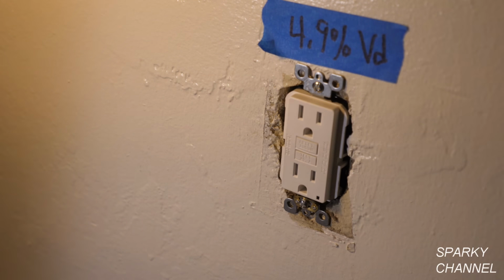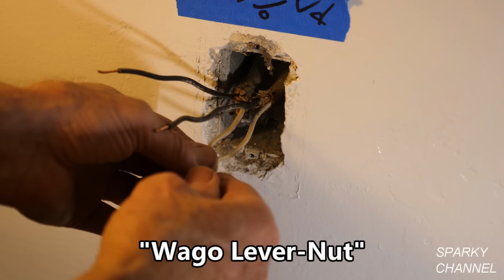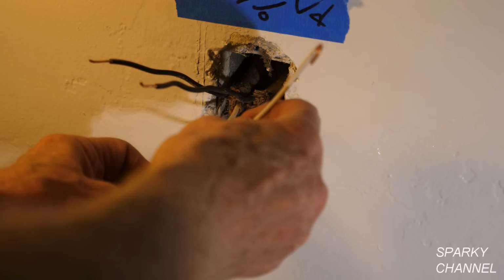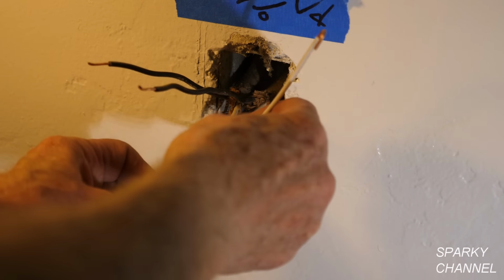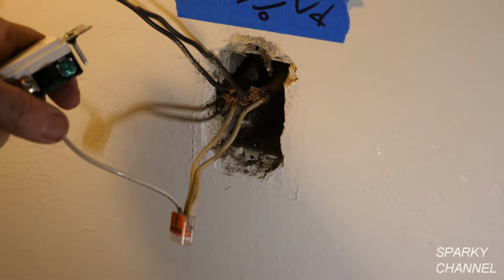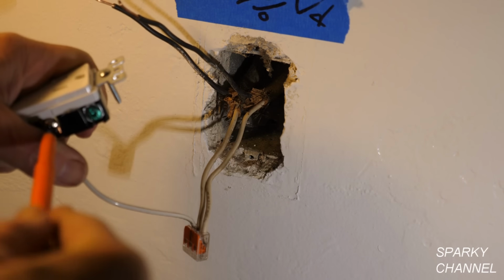Here we are at the next receptacle. Put a Wago lever nut on here. I like the Wago lever nuts in this situation because they use the absolute least amount of space. So here I'm going to put a pigtail into the lever nut, and then the pigtail is going to go onto the silver terminal. Goes around the terminal in a clockwise manner, like that. Crimp it down and tighten her up.